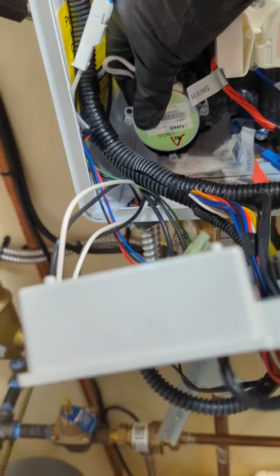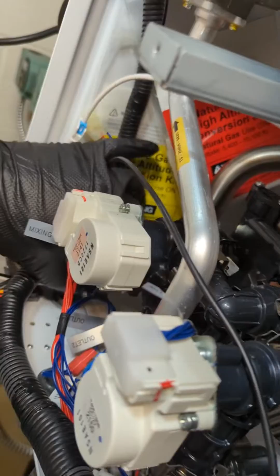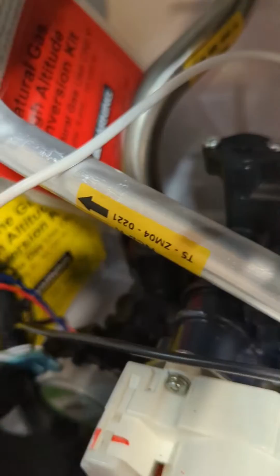That pops out, so you just get a little water there. That's why you want to drain it as much as you can, so you don't have a lot of water inside the system. Let's take a look at what's inside this. See, there's some dirt there, so it does need regular flushing every year, end of the year or end of the winter season, and also after the winter season you flush the thing out.